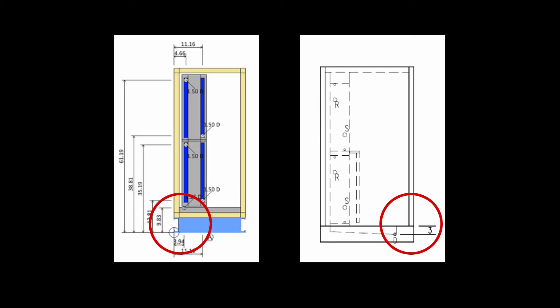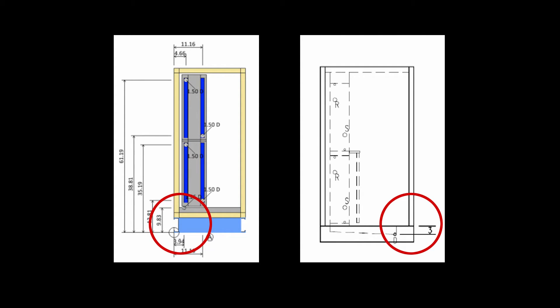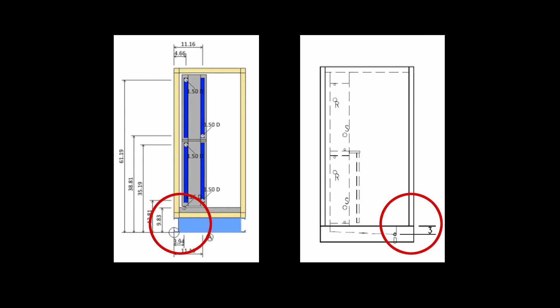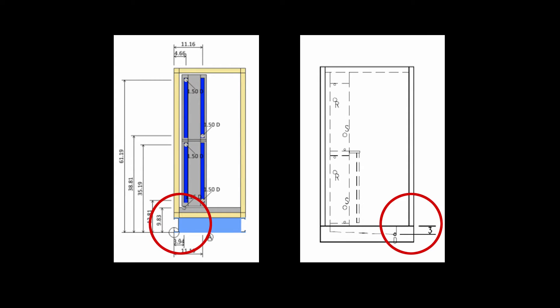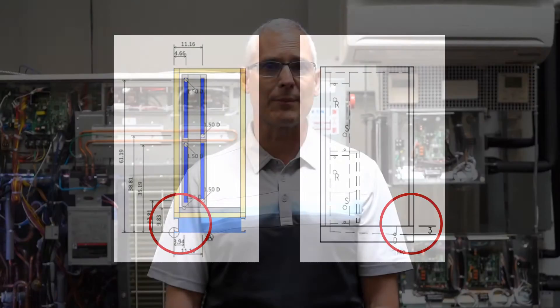Once you have the vertical clearance requirement, you must be sure there is enough space from the air handler drain to the floor to properly install the trap. Please note that there can be a considerable difference in the location of the drain connection from one manufacturer to the next, so be sure to check this dimension for each unit on each project.